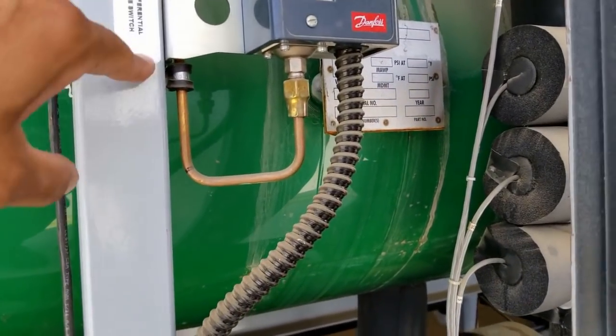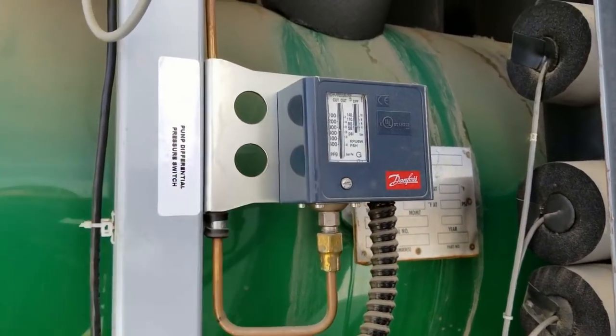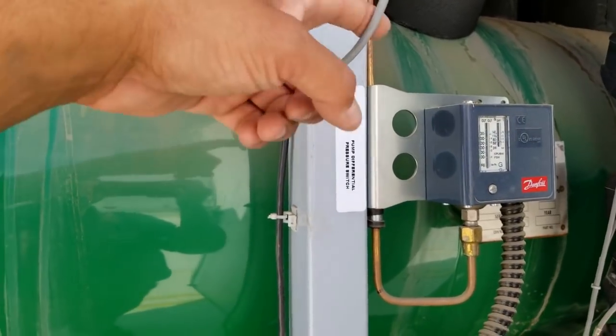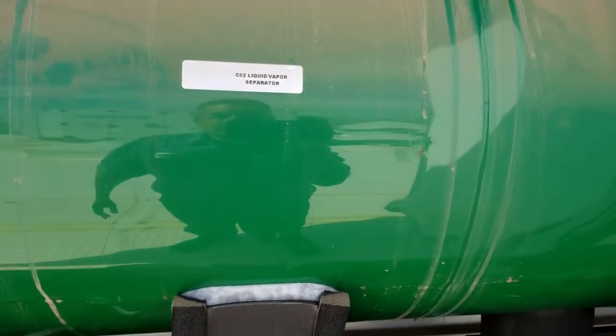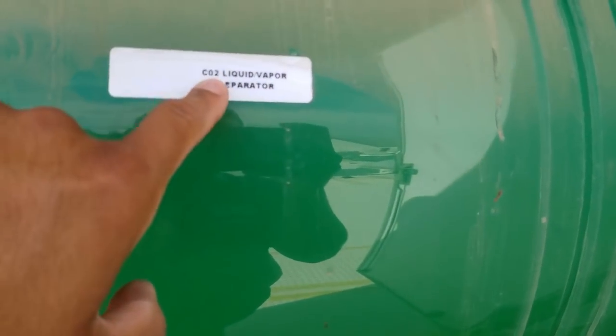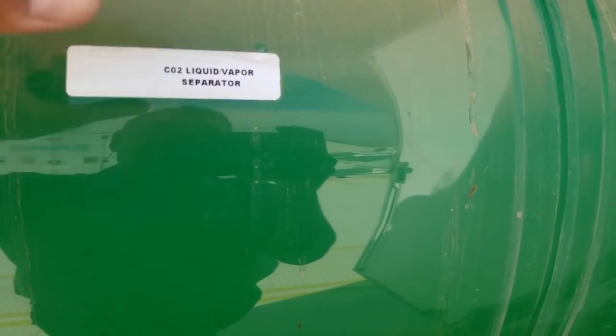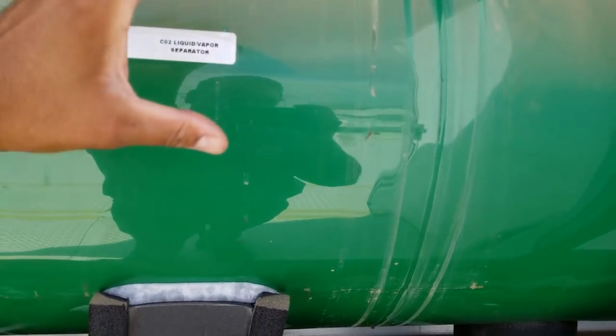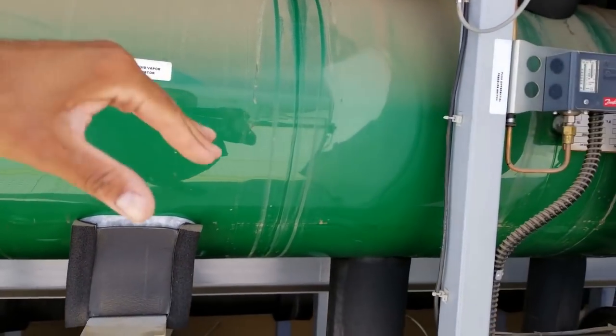And you've got your pump differential pressure switch here, transducers. You've got your CO2 liquid vapor separator. So you've got your vapor coming in, and after it goes through the chillers, you've got your liquid coming in. So, let me zoom back in, and it separates the liquid from the vapor.